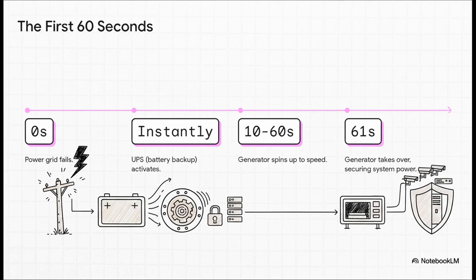The very instant the grid fails, something called an uninterruptible power supply, or UPS, kicks in. It's basically a giant, smart battery that provides instant, clean power with zero delay. Now, while that UPS is holding down the fort, your building's generator, your long-term power solution, is starting to spin up, and that can take anywhere from 10 to 60 seconds. The UPS is the bridge that perfectly covers that vulnerable gap.